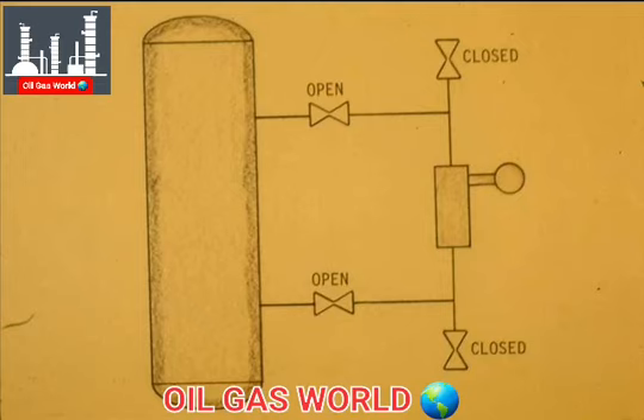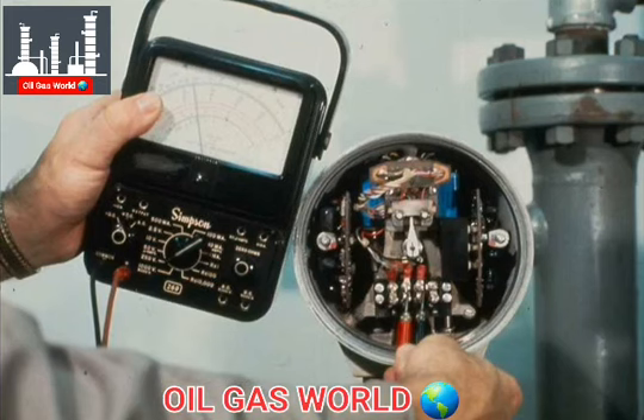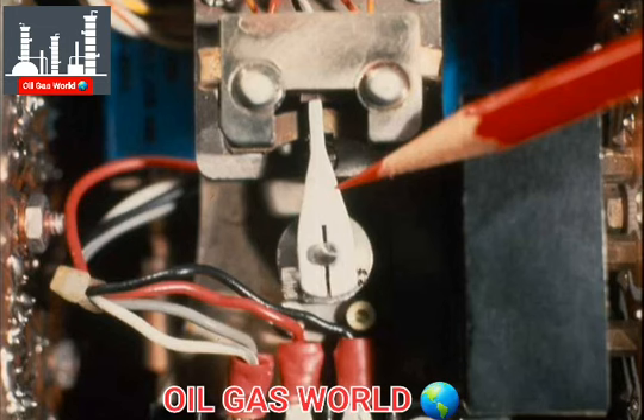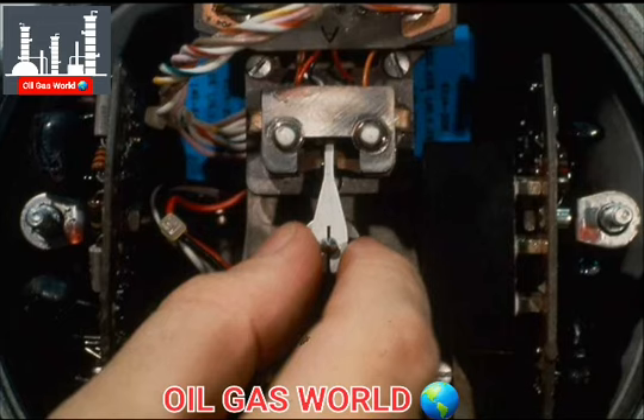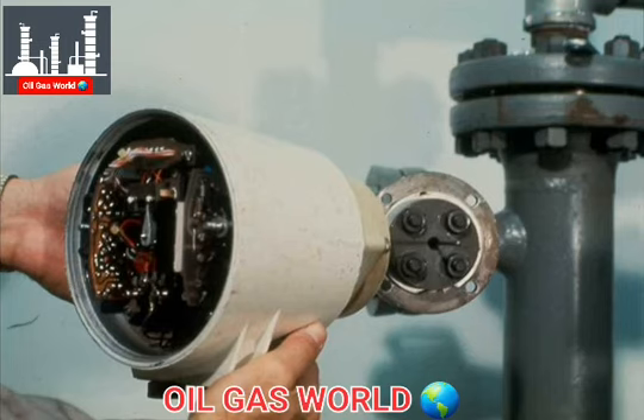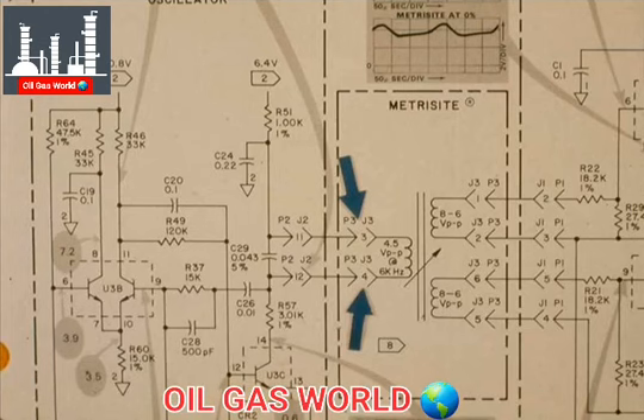First, we verified that the measurement section was commissioned correctly. Then we checked the loop wiring and also verified that the normal power was at the transmitter. Next, we verified that the Metrisite vane moved when the measurement section moved. These steps proved whether or not the entire measurement section of the transmitter worked properly. We then centered the Metrisite vane and made sure it did not bind or rub the lamination. Our next step was calibration. During calibration, we checked the entire system. If the transmitter still doesn't work properly after you attempt calibration, you can replace the entire transmitter section. Or you can further isolate the problem.